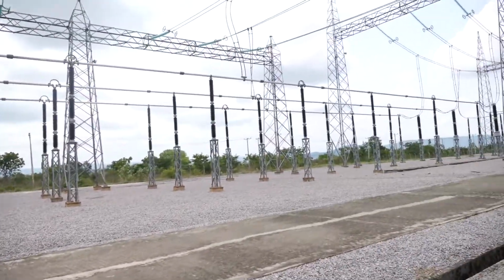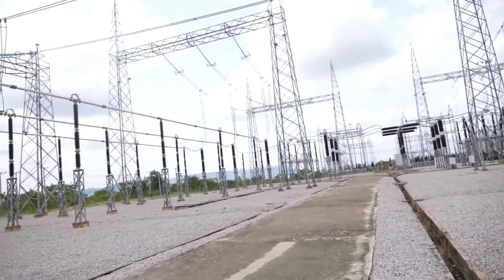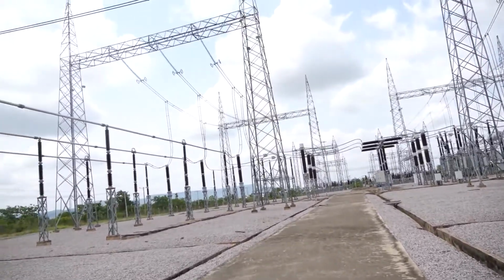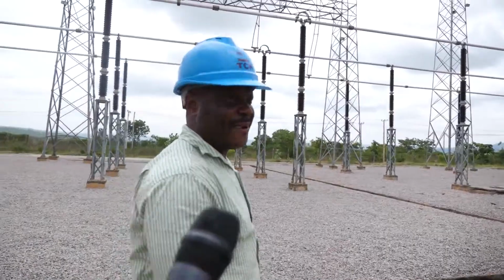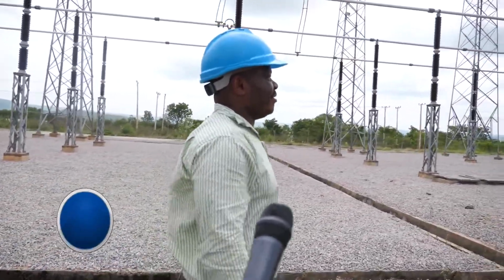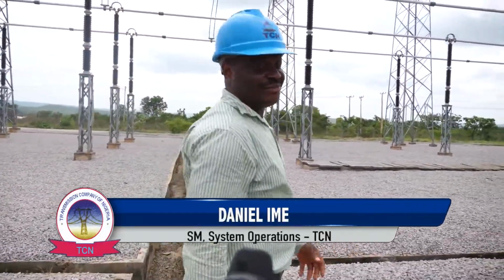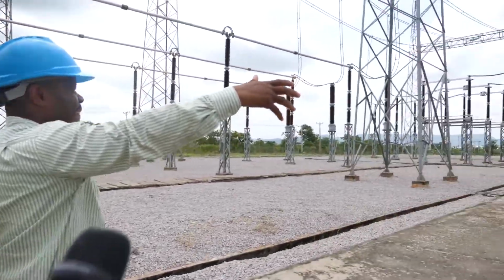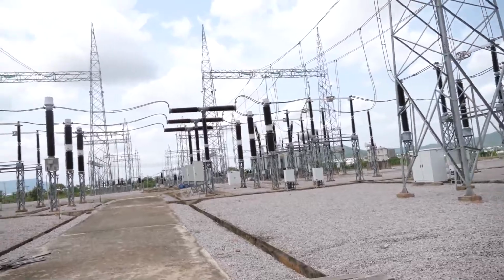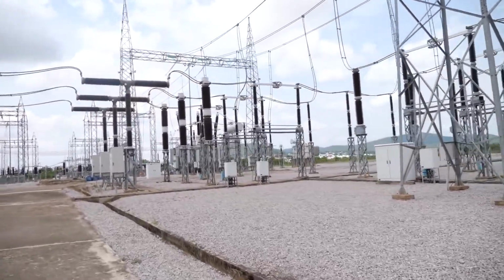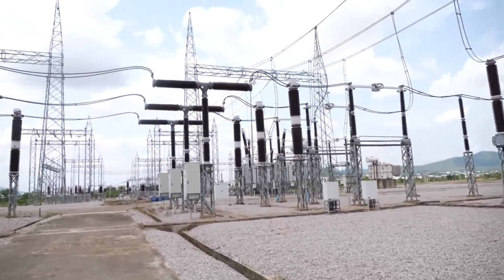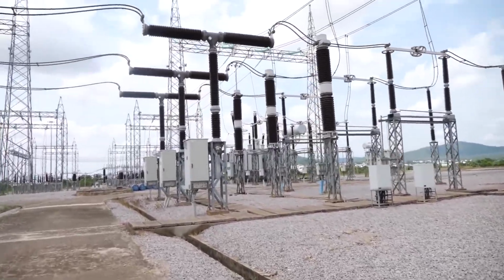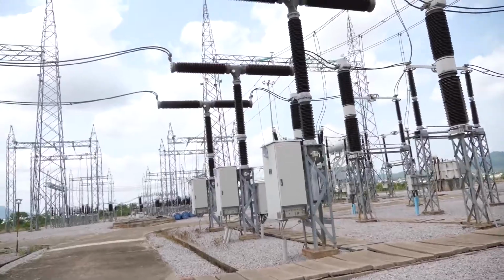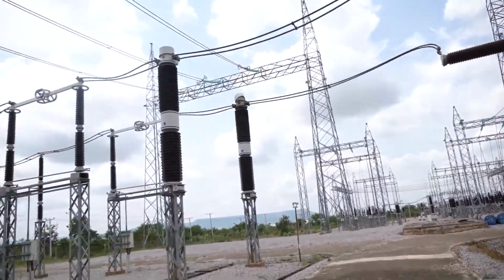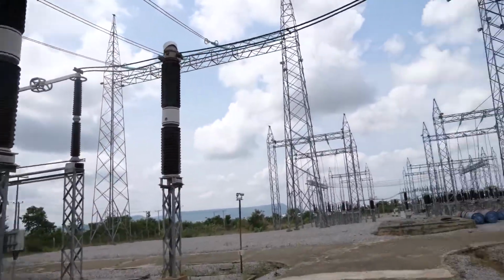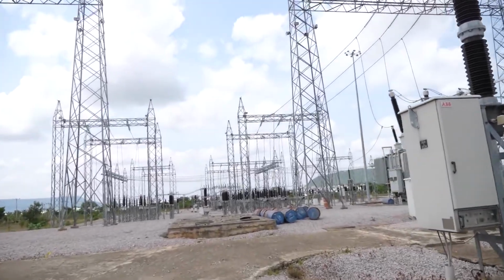So we get to the transformers. Like I told you, we have 150 MVA, one number, and we also have 60 MVA, one number. But there is arrangement for future expansion. As you can see, the 150 MVA is here, and in future, if we have to install another 150 MVA, we will not have any problem, since there's provision for it already. That's why you see this tie arrangement. You see the isolator, the breaker, and the isolator. So it is expected that in future, there should be another 150 MVA here. But for now, this is the one that we have in the station.